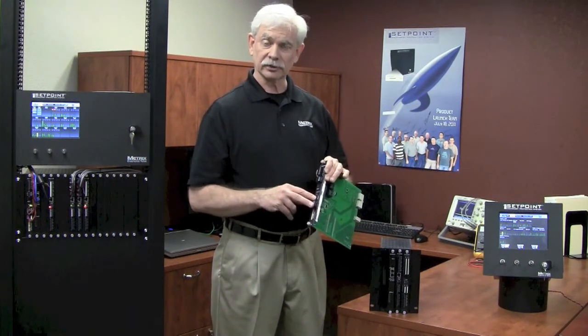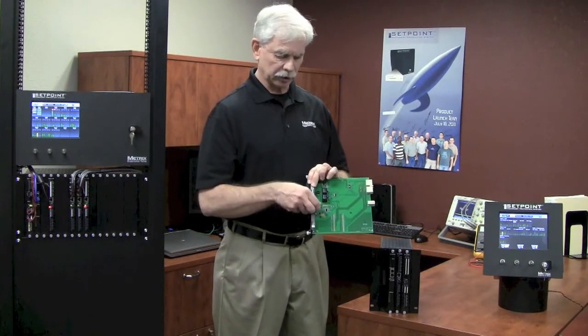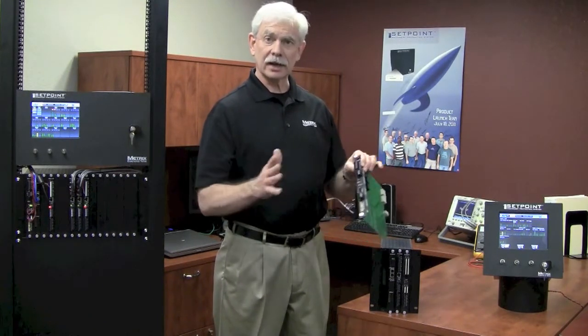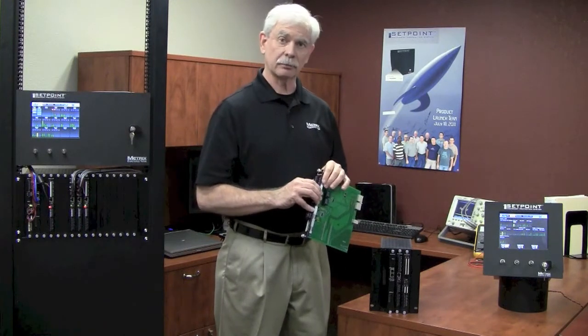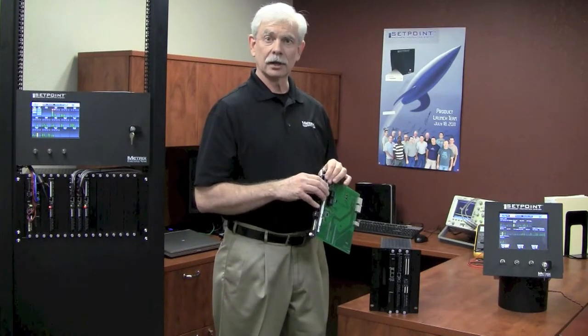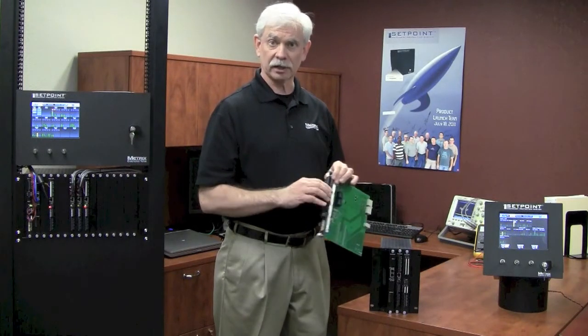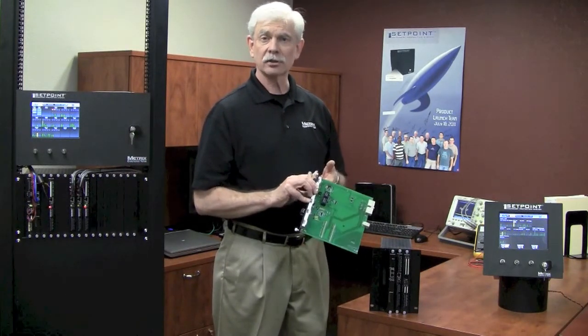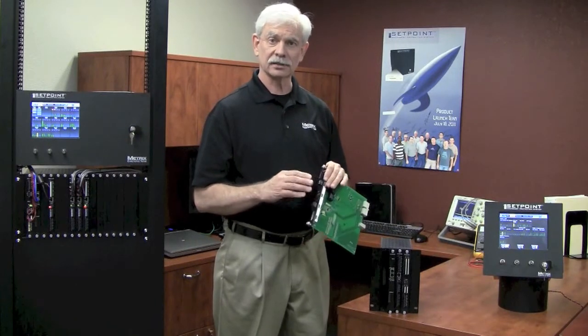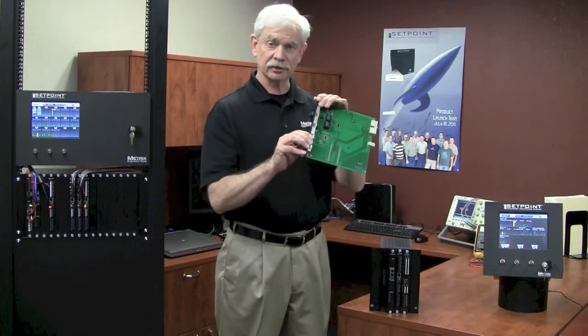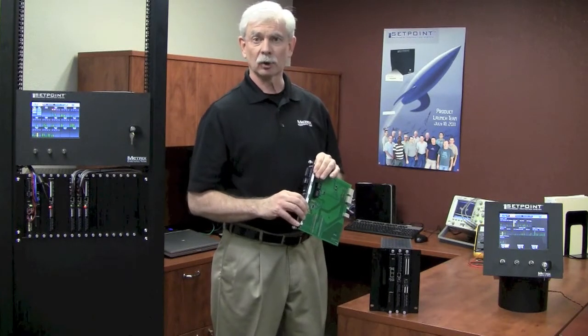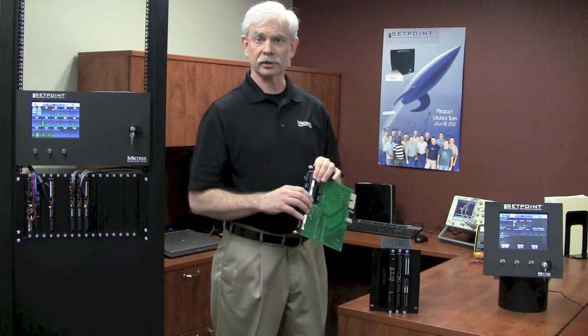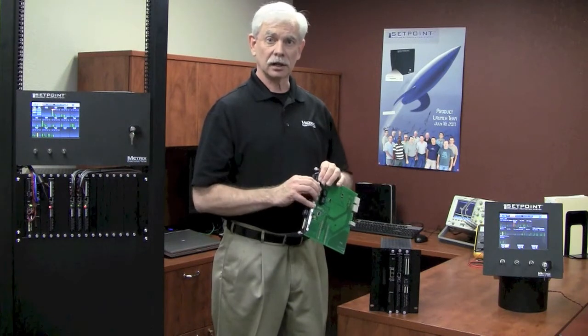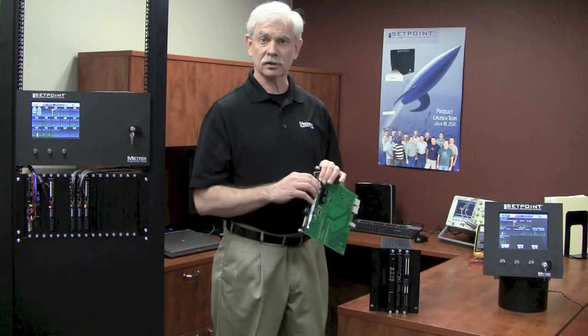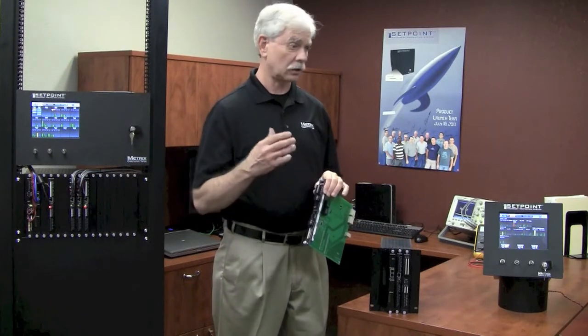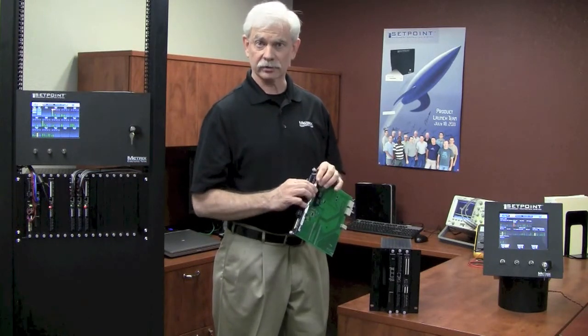We bring the 24 volts in, it comes through this very simple circuit board, goes to this connector, and then out to two separate traces on the back plane of the SETPOINT system, where that 24 volt power, redundant power actually, can be used by each module in the system. Each module does its own power conditioning, and because that's done on each module rather than centrally here in the RCM, that means a more reliable system because there is no longer a single failure point, such as one power conditioning location for all the transducer voltages or all the logic voltages and so forth.